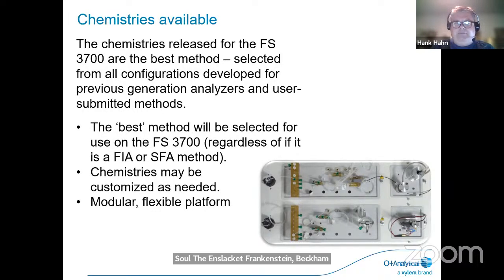Again, everything comes standard. So this is a top view of a channel where you're seeing the flow injection valve, the chemistry plate, then our photometric detector in the back channel, and the front channel is the amperometric setup with a gas diffusion module for cyanide. And again, we really want to stress modular, flexible platform. These plates can easily lift out and be replaced.